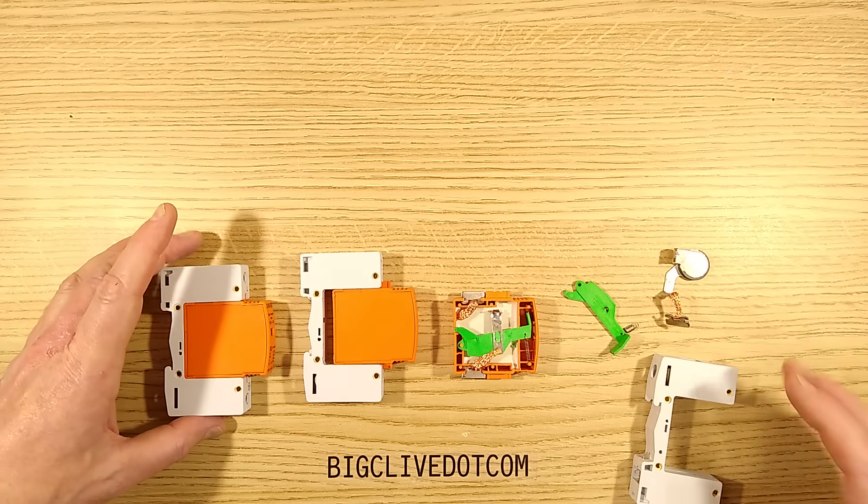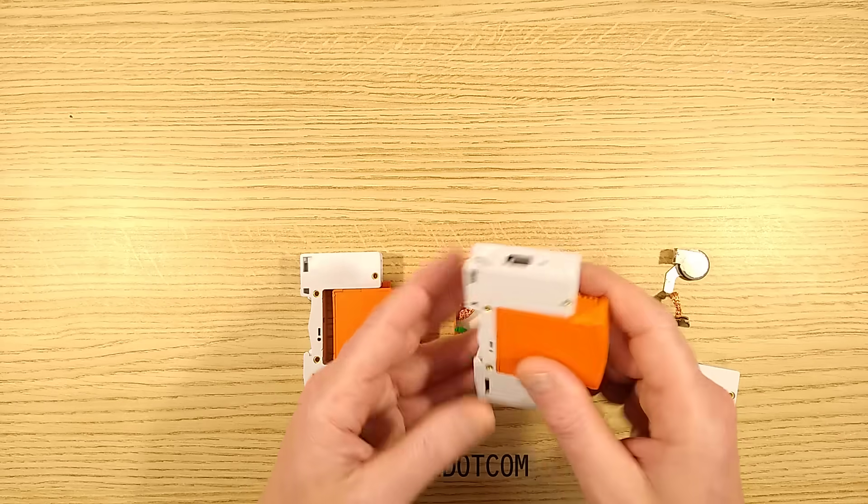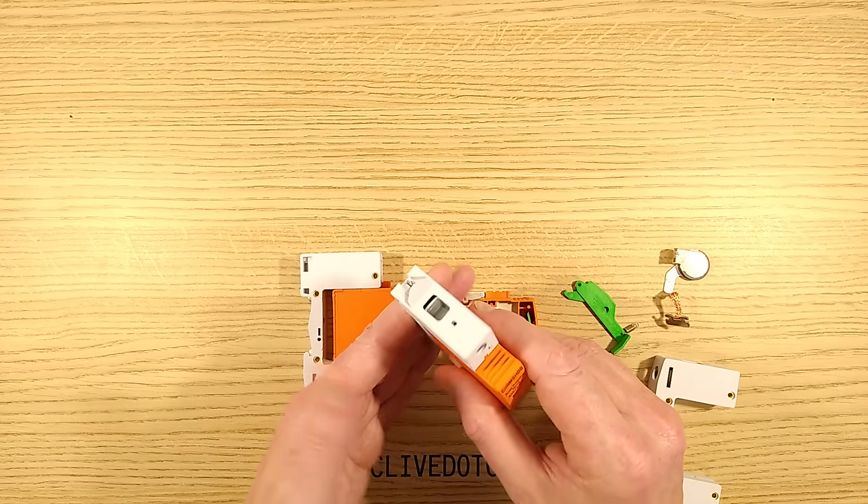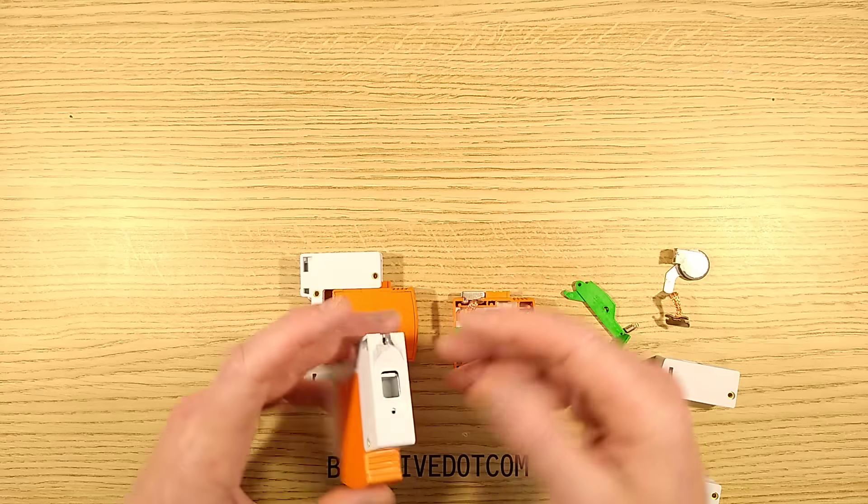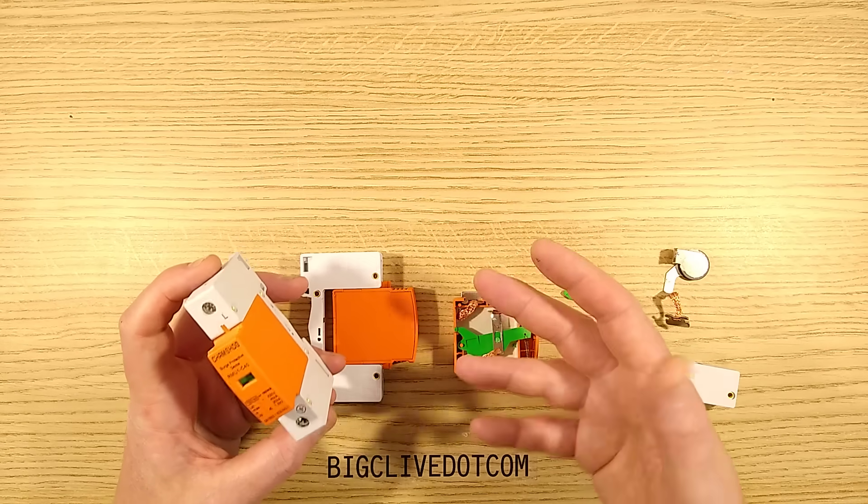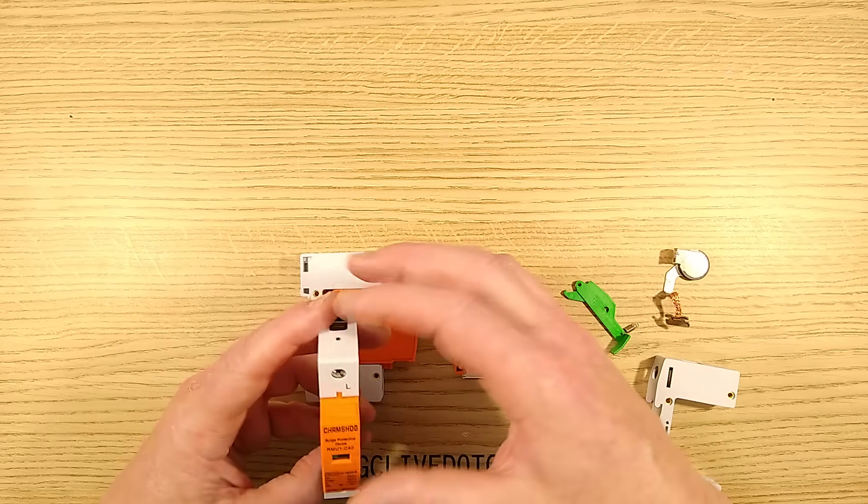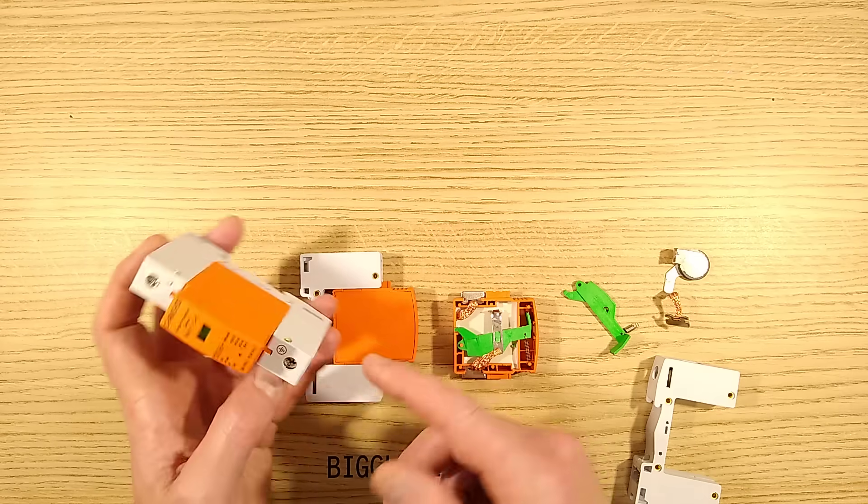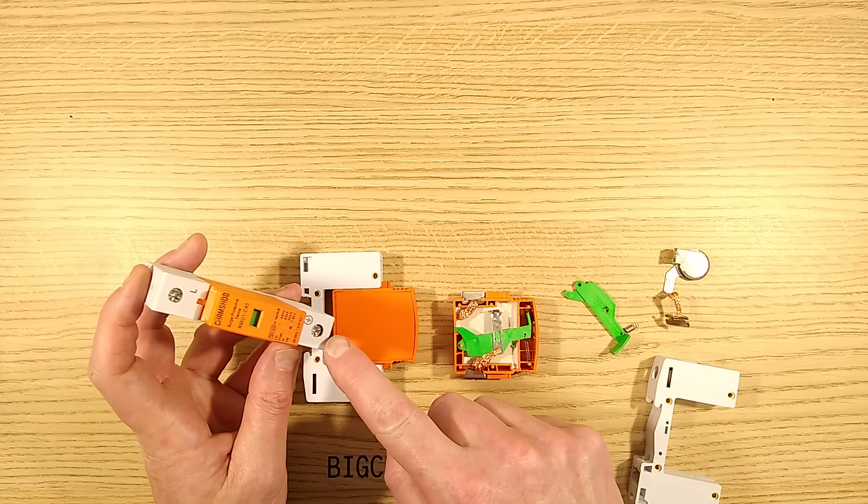So let me explain how these work. You clip the unit onto the DIN rail in your electrical distribution equipment. You put your live in here. If you're in a country with more than one phase, then you put each phase into a separate unit. And then there is an earth connection or a ground connection here.